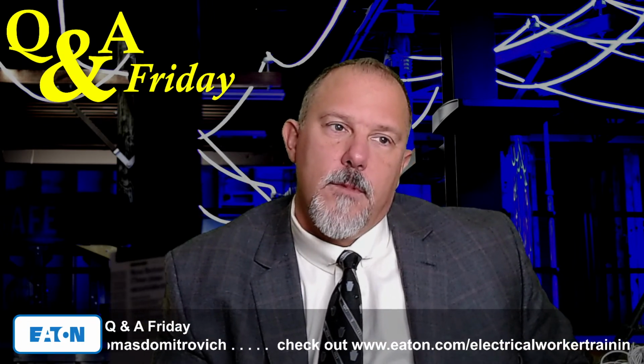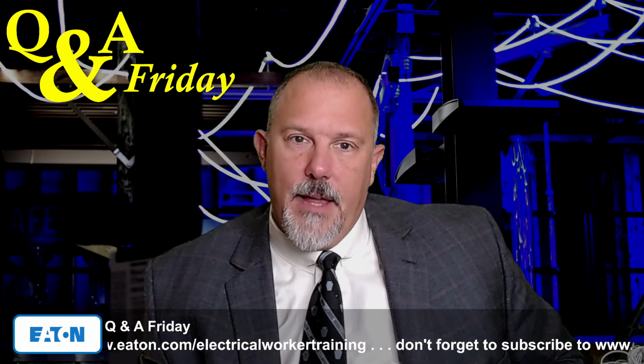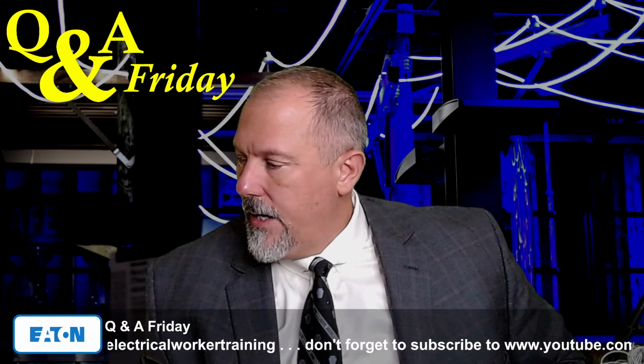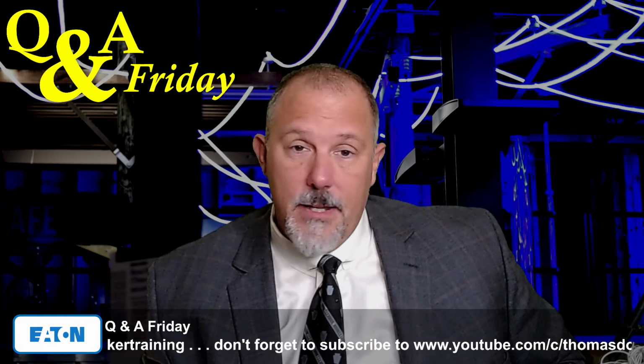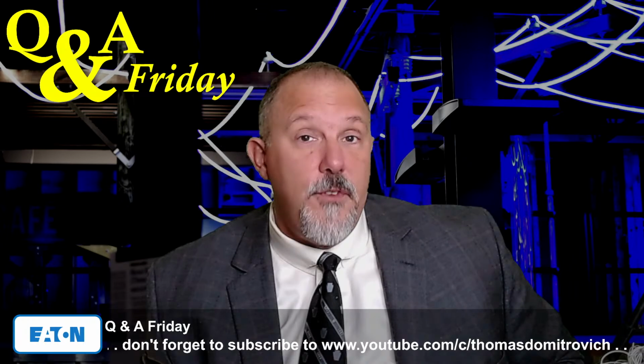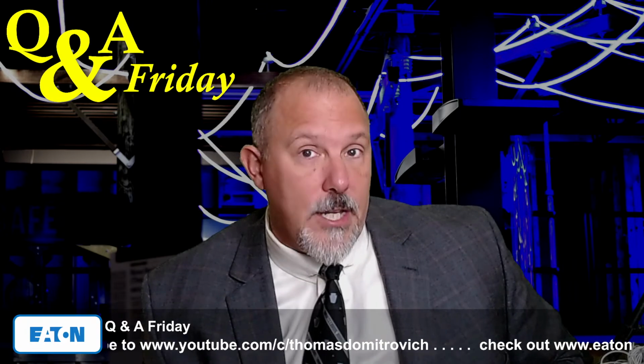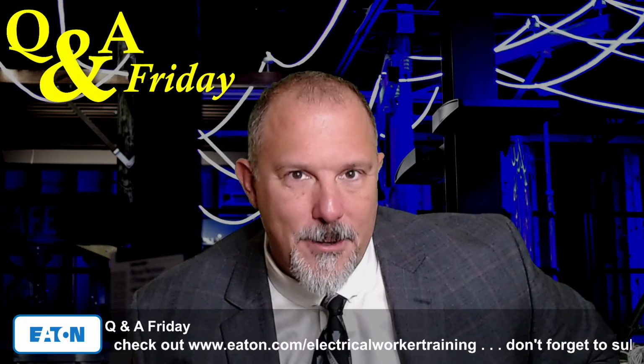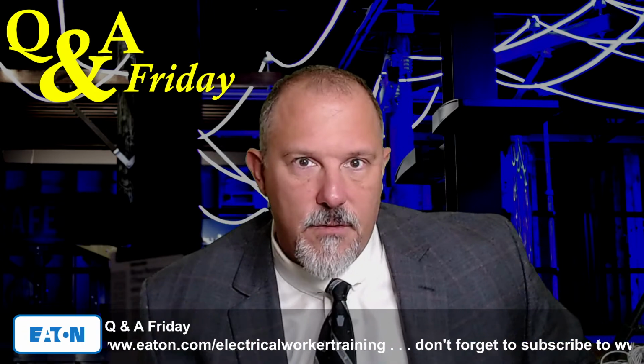So this gentleman wanted to use a three-phase panel rated 600 volts at a lower voltage and in a single-phase application. And he says, do you think I can do that? What would the inspector say? And so I'm telling you, I could not find anything in the National Electrical Code that says you can't do that. From a voltage perspective, I can't exceed the rated voltage, so I can use a 600 volt panel at 240 volts. I can use a 600 volt rated panel at 120 volts. It doesn't matter, as long as I don't use a 600 volt panel in a 4160 application, right? Or a 240 volt panel at 600 volts or 480 volts.